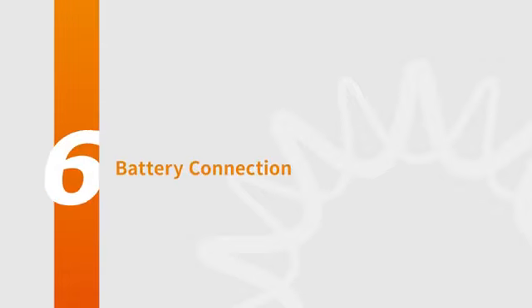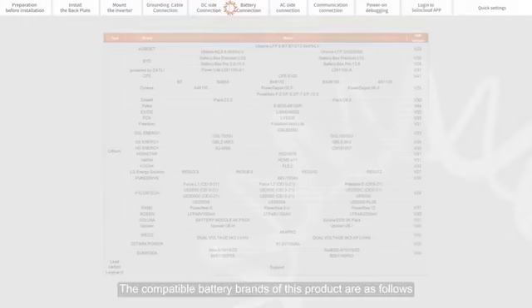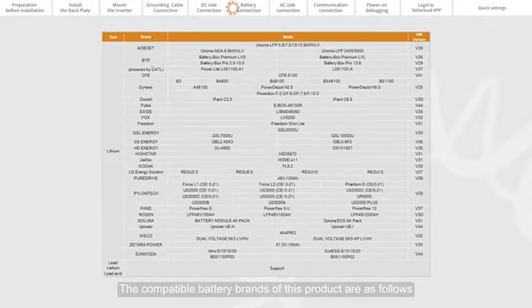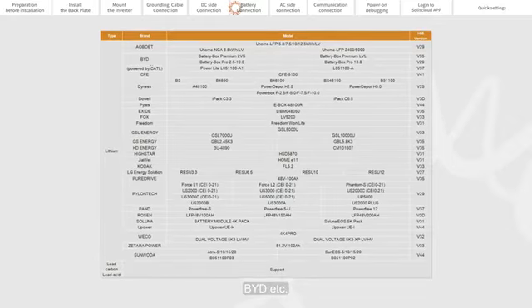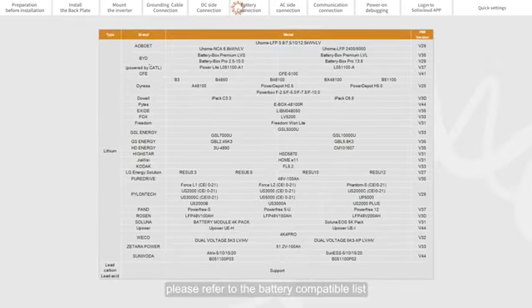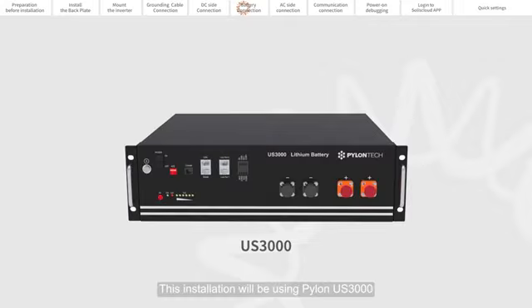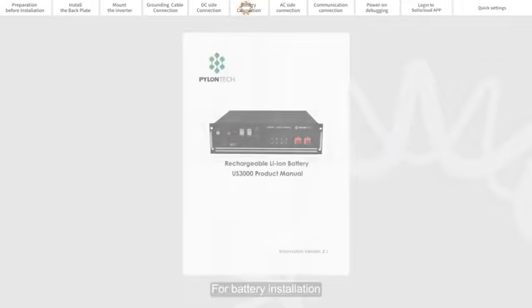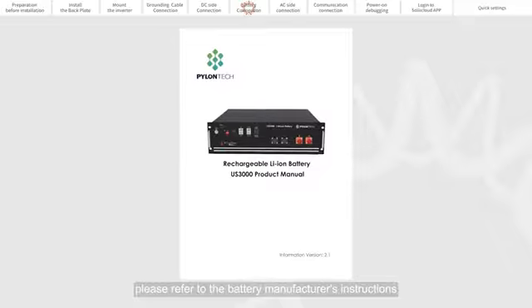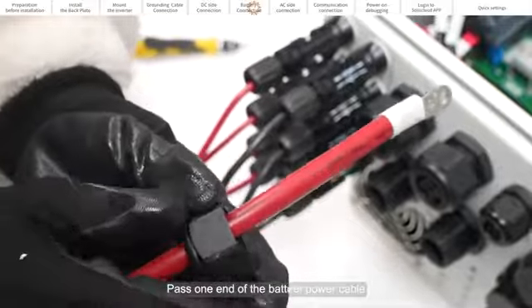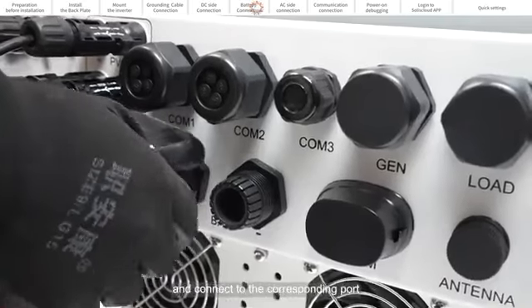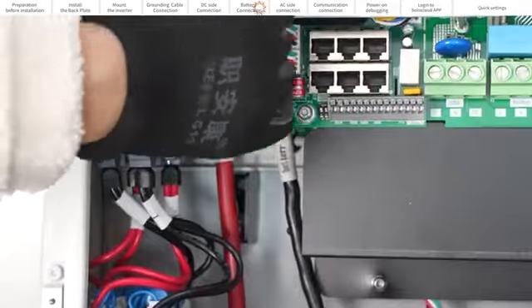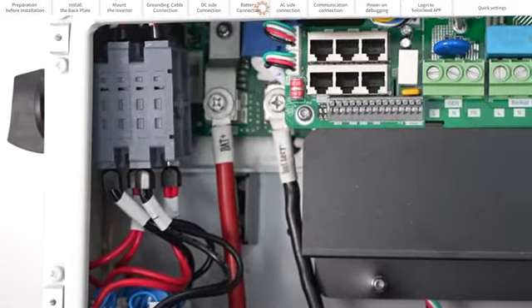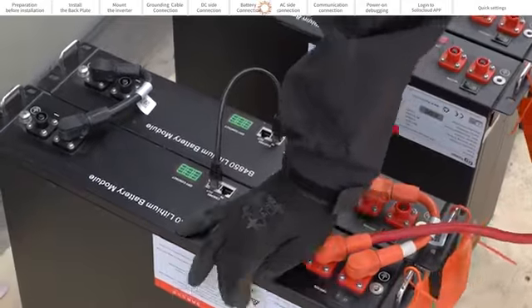Part 6. Battery connection. Compatible battery brands of this product are as follows: Pylon, BYD, etc. Please refer to the battery compatibility list on the Solis website for details. This installation will be using Pylon US 3000s. For battery installation, please refer to the battery manufacturer's instructions. Pass one end of the battery power cable through the BAT opening at the bottom of the inverter and connect it to the corresponding port. The other end is connected to the battery.